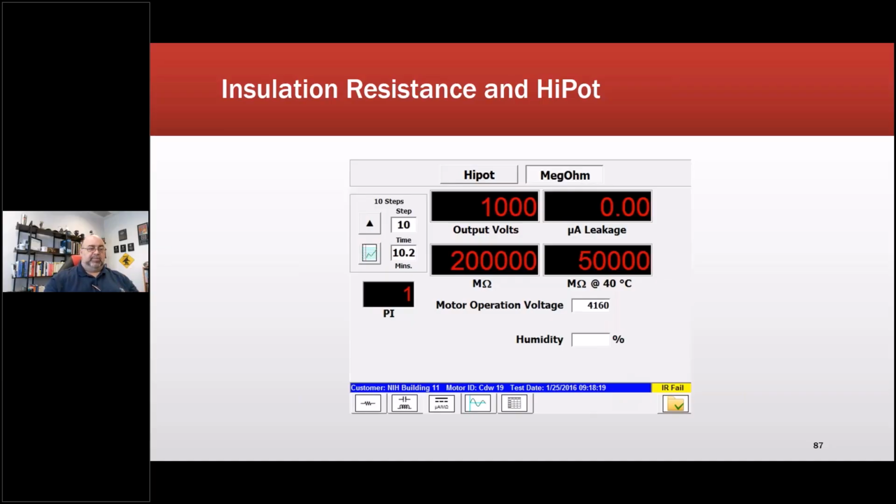It has certain capabilities, but also some bad capabilities. It requires careful handling, but basically makes the insulation system, even if PD is present for a low voltage machine from an inverter, eliminate any problems, versus nano dielectrics, which can only be used on round wire right now. Okay, so megohm, and then a high pot would be the next one.